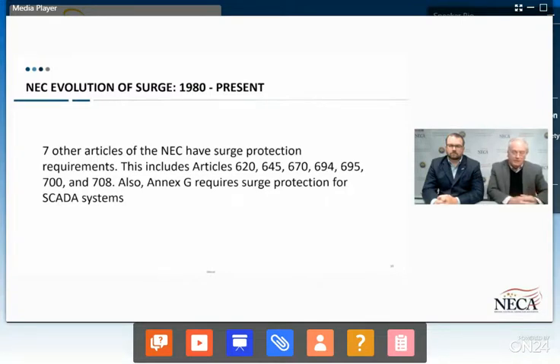As the NEC evolved into the 70s and 80s, we saw Article 280 appear, and it was first titled Lightning Arresters. While it kind of made sense what they were trying to do, that's just an external cause of a surge event. The NEC, under its current scope and the scope then, was never intended to provide lightning protection or the rules to protect against those events. There's another standard, NFPA 780, that talks about that type of protection.